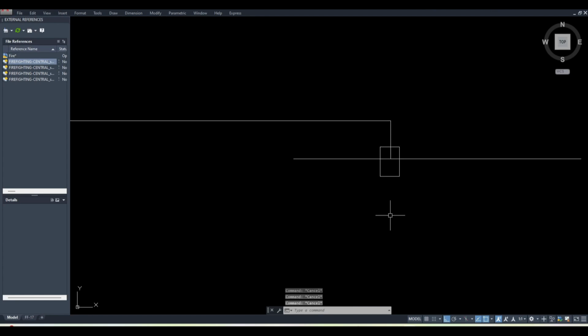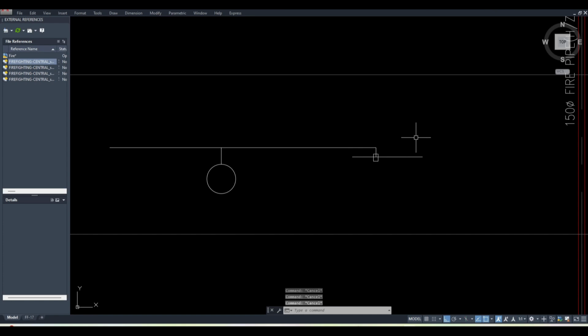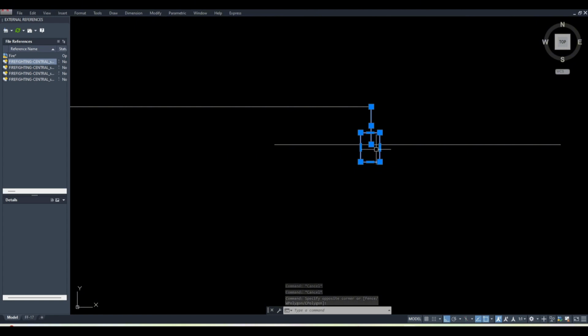Now the upright, same as pendant, but it goes in the upward way. So in the places where there is no ceiling, we can use the upright sprinkler. Okay, and in the places where the ceiling is available, you need to use the recessed or pendant sprinkler. Okay, the pendant type, whether recessed, semi recessed, or normal pendant.